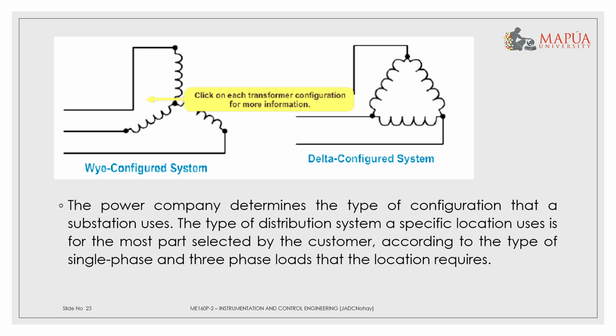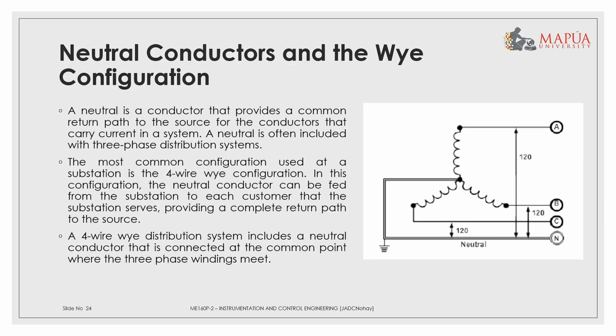The power company determines the type of configuration that a substation uses. The type of distribution system a specific location uses is, for the most part, selected by the customer according to the type of single phase and three phase load that the location requires. So, neutral conductors in the Y configuration. The most common configuration used at a substation is the 4-wire Y configuration. In this configuration, the neutral conductor can be fed from the substation to each customer that the substation serves, providing a complete return path to the source.